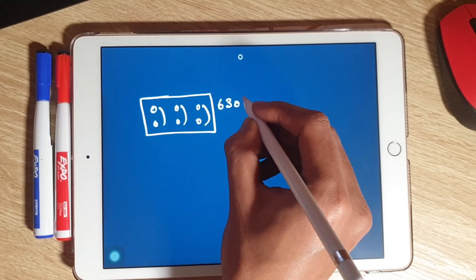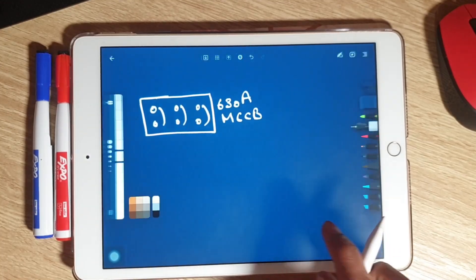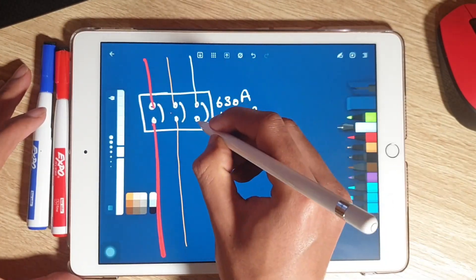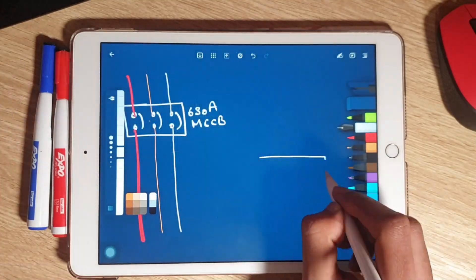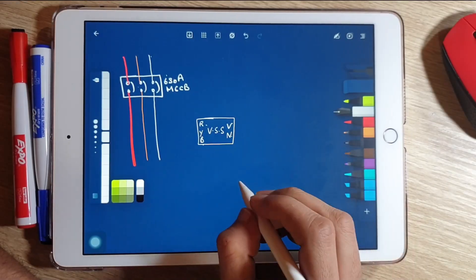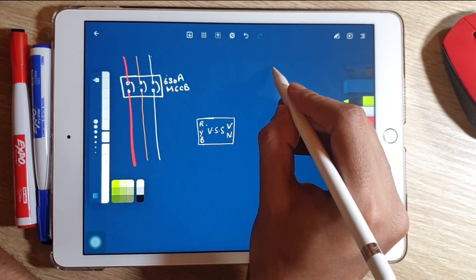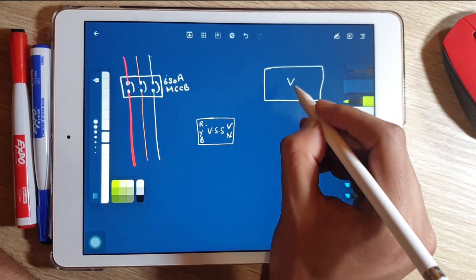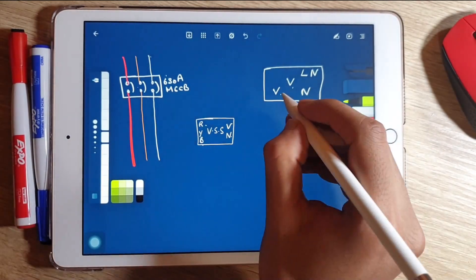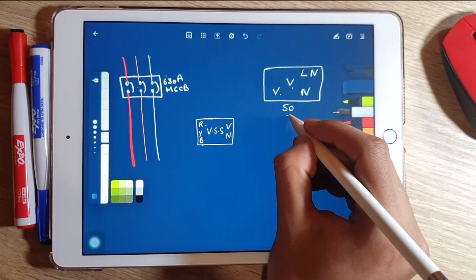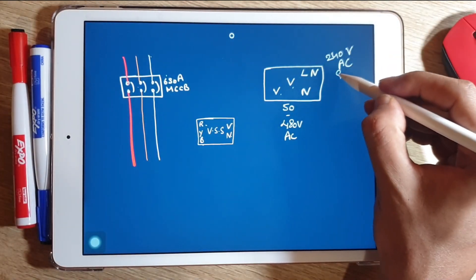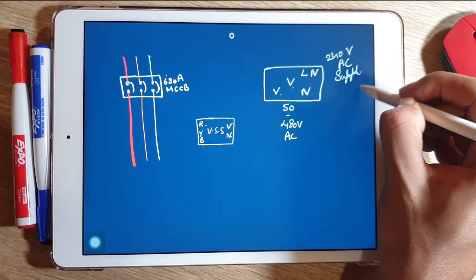Now focusing on voltmeter wiring — I am using a three-phase supply with a 630-ampere MCCB. The voltmeter selector switch has R, Y, B terminals and a V and N terminal. The voltmeter itself has a V-N terminal for 50 to 480 volts AC supply and an auxiliary supply of 240 volts AC.